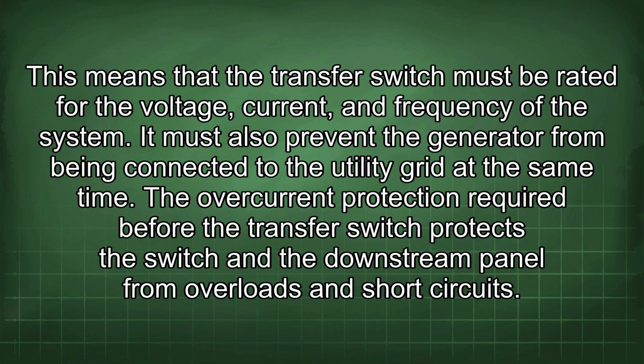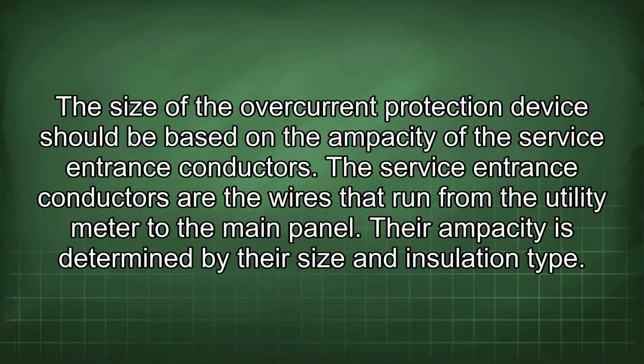This means that the transfer switch must be rated for the voltage, current, and frequency of the system. It must also prevent the generator from being connected to the utility grid at the same time. The overcurrent protection required before the transfer switch protects the switch and the downstream panel from overloads and short circuits. The size of the overcurrent protection device should be based on the ampacity of the service entrance conductors. The service entrance conductors are the wires that run from the utility meter to the main panel.